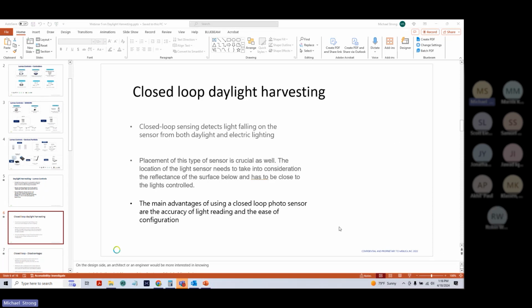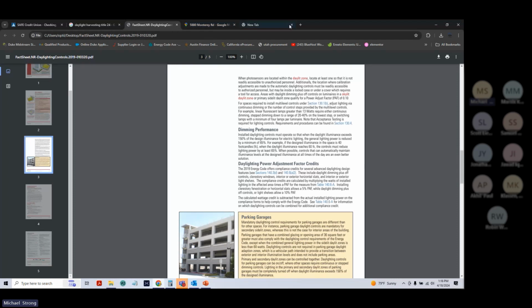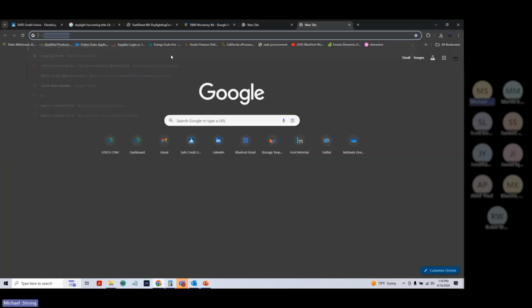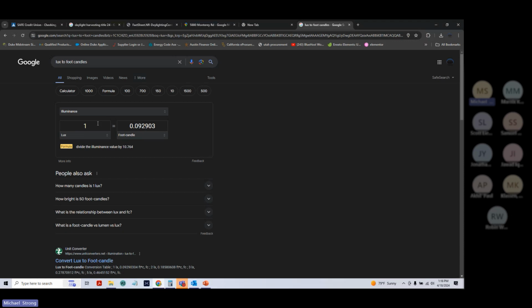It may be that we want to use 24-foot candle as the basis for an office space. And so in order for us to do that, we set the lux accordingly. And I don't know if you guys are aware of this, but you can convert lux to foot candle. You can set your foot candle at 24-foot candle and see the lux reading. And so in our software, this is where you would set your lux by simply doing the conversion, or knowing that conversion ahead of time.